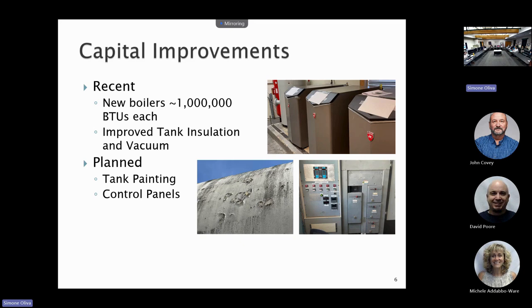We sent it out for design, and when the design came back and the mechanical contractor was chosen, our staff — Barry, myself, and Sean, our senior maintenance mechanic — actually did some reverse engineering on the project and found some value in it. We were able to eliminate an auxiliary boiler that we didn't feel was necessary. When we dug into the actual sizing of the vaporizers and the piping and what we were able to put out, we were able to downsize by 1 full boiler, and we still ran at full tilt.